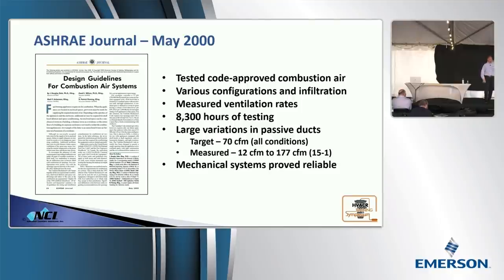The installation that they put in, based off of what we just looked at, should have provided those guys 70 CFM under all conditions. Makes sense, right? Because if we install a combustion air duct, air is supposed to go through it, right? How does the air know that? How does the air know? As we get into air basics, we're going to look at some principles that drive airflow that you guys know. We're just going to take a 90 degree shift. Check out that variation, guys. 15 to 1 was the variation on their airflows. And as the combustion air changed, your airflows changed.